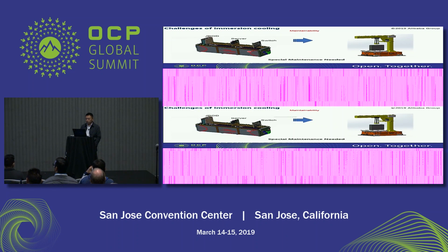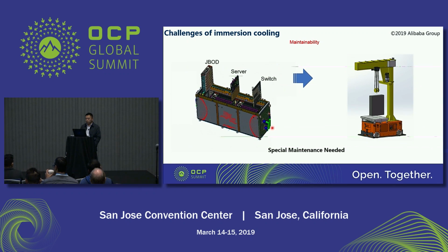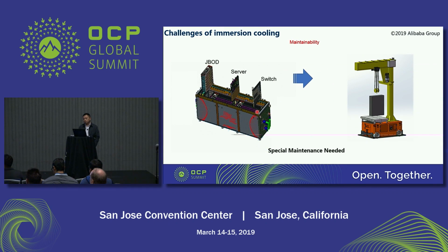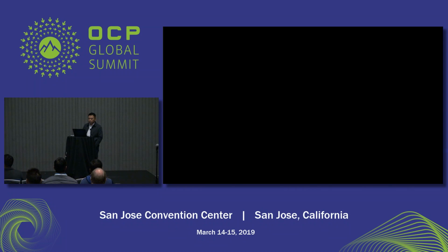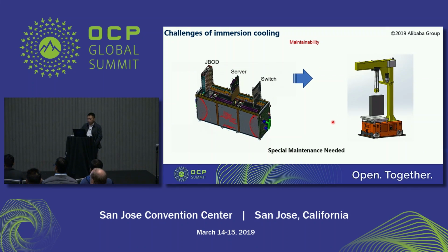As can be seen from this picture, there are 54 units in one tank. We designed 6 units for switches, and 48 units for servers, supporting switch 1 plus 1 redundancy. Each switch has 48 ports in total. Special maintenance is needed.